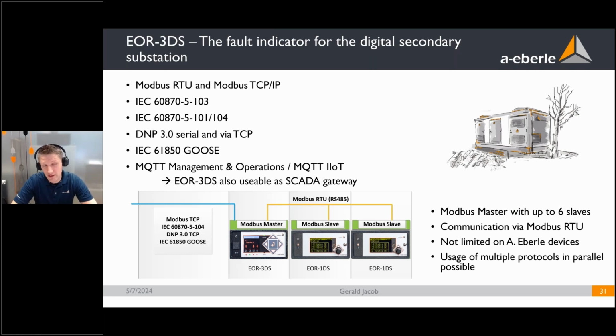I already said some words about the possible protocols that are available: not only Modbus RTU, but also Modbus TCP, 103 protocol, which I did not mention yet, 101 protocol, 104 protocol, DNP serial or via TCP, and 61850 Goose. In future, we could also implement 61850 MMS, but at the moment our feedback from customers is that 61850 MMS is not required so far in secondary substations. And the newest 2 protocols, MQTT, Management and Operations, and IoT, we will see in the 5th chapter, as I said.